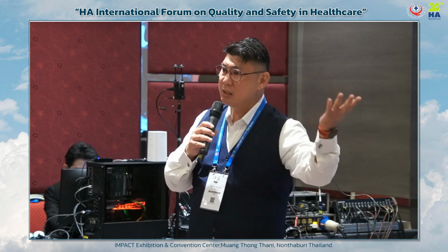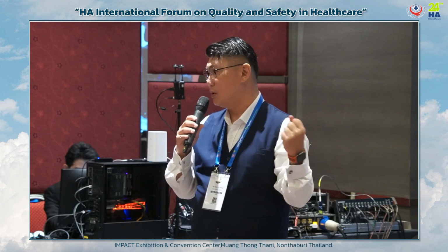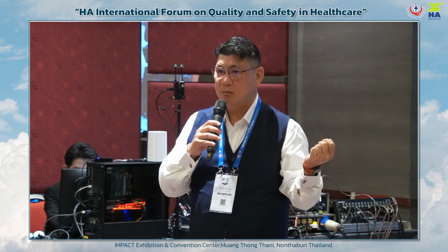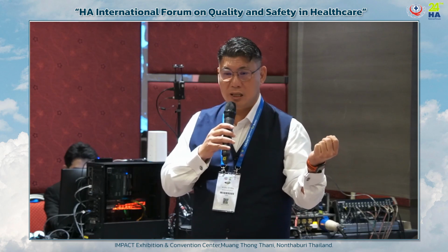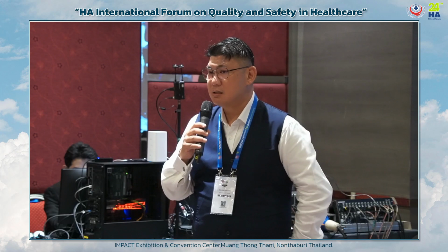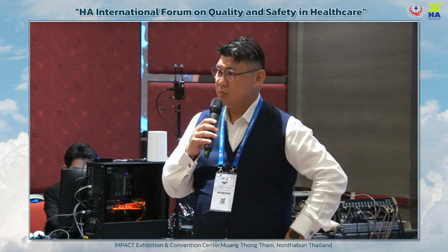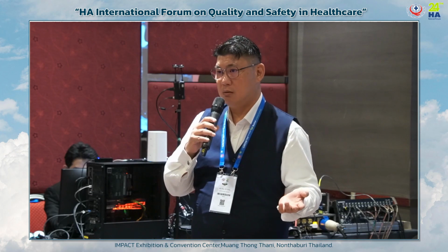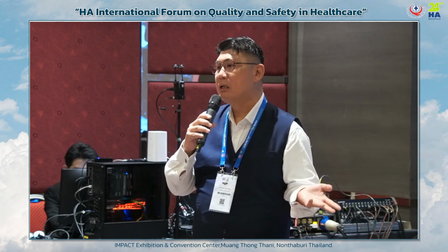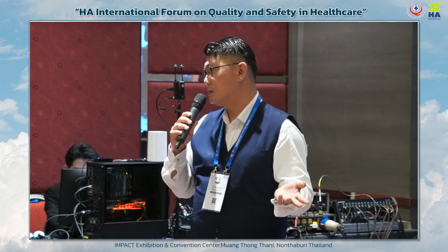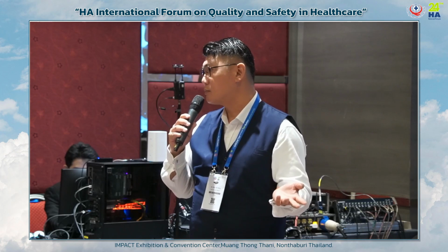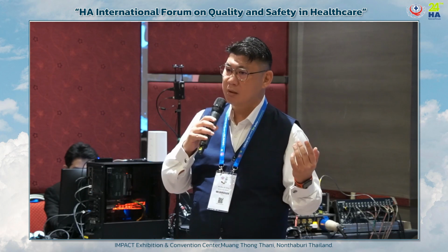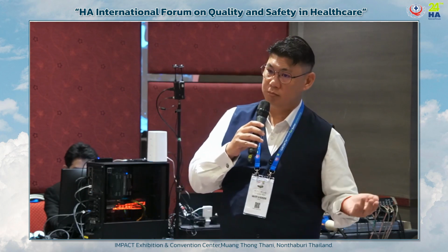There is a case, I don't know, some of you I shared before. If I have time, I'll share this case very quickly. In Vietnam, some of you may know, 9 patients died because of dialysis. It's because maintenance was not completed properly. They were cleaning the reverse osmosis water system with chlorine, and they didn't flush everything out on time. And the maintenance people went home.